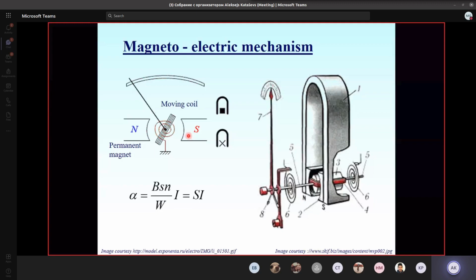One method to check whether a magnetoelectric device is operational: shortcut its output, the coil, and try to rotate it a little bit to make the index move. If you see the oscillation of the index fade very fast when you shake the device, your device is okay, meaning the coil is intact. If it oscillates readily and doesn't fade fast, it means your device is broken and the coil is burned out, since there's no more contact inside the coil and the electromagnetic induction doesn't work.